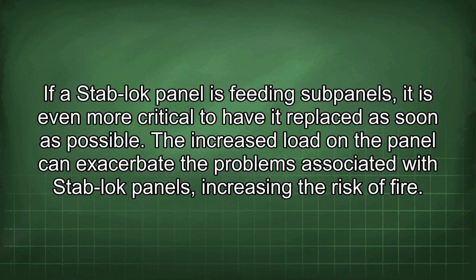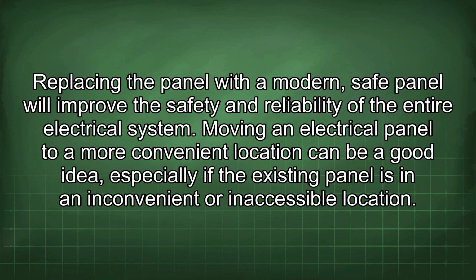If a Stab-lok panel is feeding subpanels, it is even more critical to have it replaced as soon as possible. The increased load in the panel can exacerbate the problems associated with Stab-lok panels, increasing the risk of fire. Replacing the panel with a modern, safe panel will improve the safety and reliability of the entire electrical system.